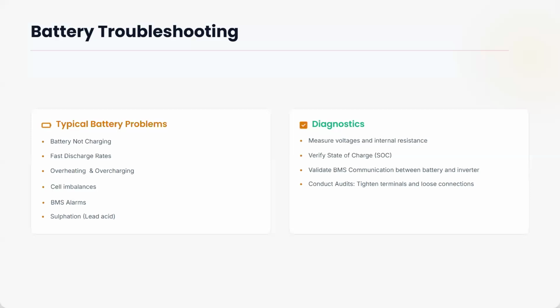So if they say the internal resistance of such a battery is probably 4 milliohms, and then when you connect your analyzer to it, it's telling you 100 milliohms, you can see it's definitely out of range. The battery has an issue. So that indicates that the battery is bad. If it's even slightly beyond the standard value given as part of the specification, then you know that there's a problem. The performance will not be okay again, and that's the reason you were there to diagnose.